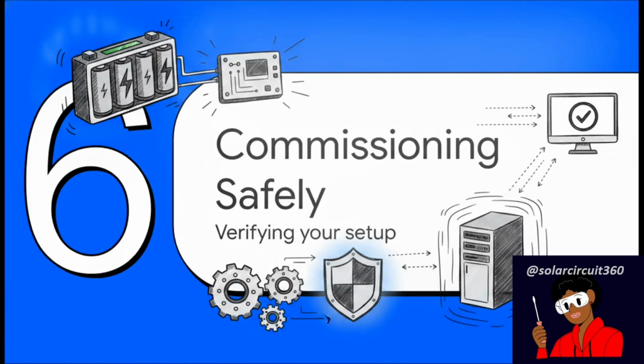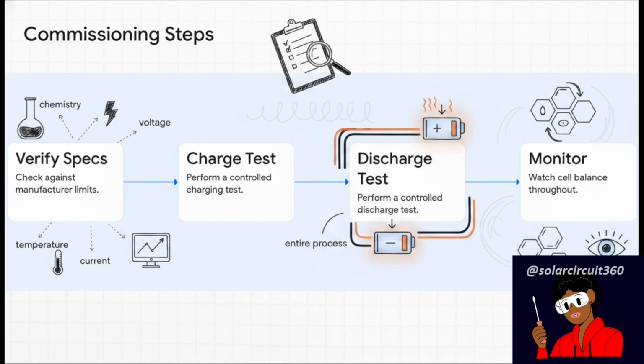All right, finally, Section 6, commissioning safely. After we've dialed in all these parameters, how do we actually prove that the numbers we've entered will protect our expensive hardware in the real world? We do it by meticulously commissioning the system. First, verify absolutely every parameter against your manufacturer's spec sheet. Next, run a controlled charging test and keep a close eye on those cell voltages and temperatures. Third, hit it with a heavy, controlled discharge test to make sure your cables and terminals aren't overheating under real stress. By walking through these steps, you are actually testing your safety supervisor to prove it's awake, fully operational, and ready for action.